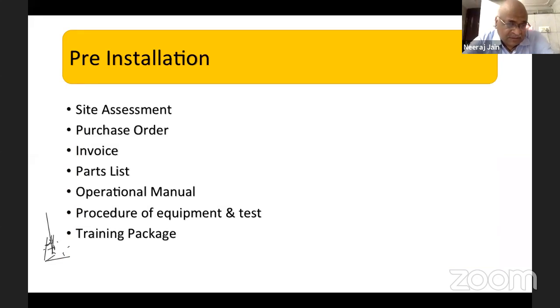In pre-installation, before installing: IQ means installation qualification, OQ means operational qualification, PQ means performance qualification. Before installation, first do some site assessment, whether the space is suitable for this machine or not. If you require, you can call company people also and ask them to approve this place for the machine. Then keep a copy of the purchase order in your file. When you're getting the machine, keep a copy of the invoice, and check the list of what all parts you have received, and the operation manual.